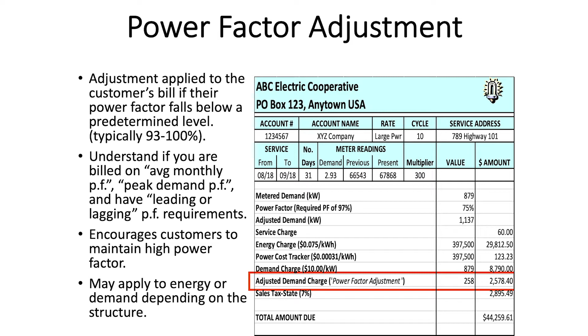So understand how you might pay power factor adjustment. Is it a line item adjustment? Is it the difference between measured demand and billing demand? And if you look on your bill and measured demand is low and billing demand is higher, that means you have a power factor adjustment there. So if your power company requires 97% power factor, they're not going to ding you above 97%, but if you're below 97%, they're going to make an adjustment.